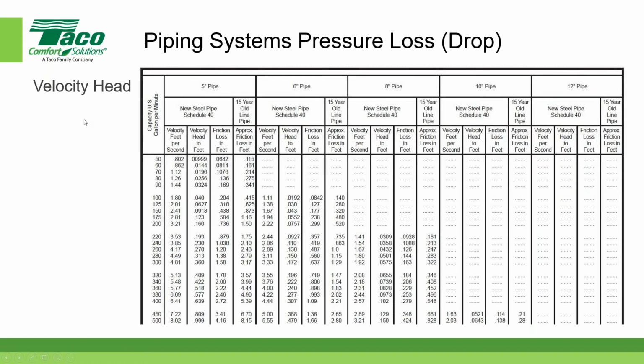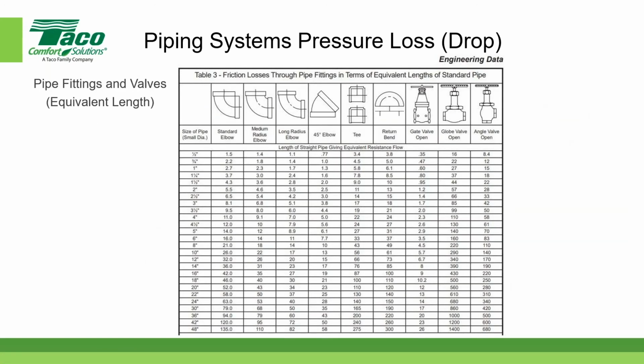All right. So let's continue right along here and let's talk about the pressure drop through fittings. When we do the manual pressure drop calculation in a minute, we're going to use what is known as the equivalent length method. And that's this method over here. It says that for every fitting in our system, it has an equivalent length of straight pipe. So for example, the first standard elbow, this is a 90-degree standard elbow. In our case, we had 6-inch pipe. So let's go over here, 6-inch pipe. And if you'll notice, the equivalent length of this 90-degree elbow would be equivalent to 16 feet of straight pipe. We'll get into that in a few minutes.